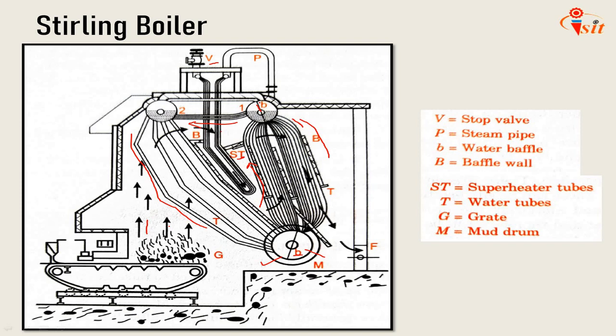Fire brick arch gets incandescent hot and helps in combustion and preventing the chilling of the furnace. The steam drums and mud drum are supported on steel beams independent of the brickwork. The Stirling boiler is lighter and more flexible than straight tube boilers, but it is comparatively more difficult to clean and inspect the bent tubes, which is a disadvantage of this boiler.